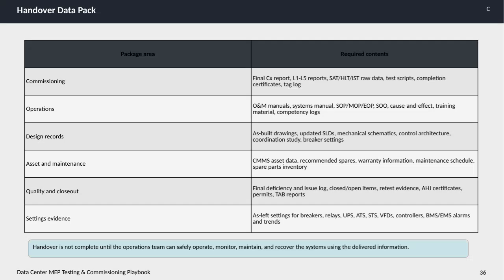Now, let's take a closer look at the handover data pack, which is a crucial component of the data center MEP testing and commissioning process. The handover package is divided into several key areas, each with specific required contents to ensure a smooth transition. First, the commissioning section must include the final commissioning report, a series of detailed reports from levels 1 through 5, raw data from SAT, HLT, and IST tests, test scripts, completion certificates, and a comprehensive tag log. This ensures all testing and validation records are thoroughly documented.